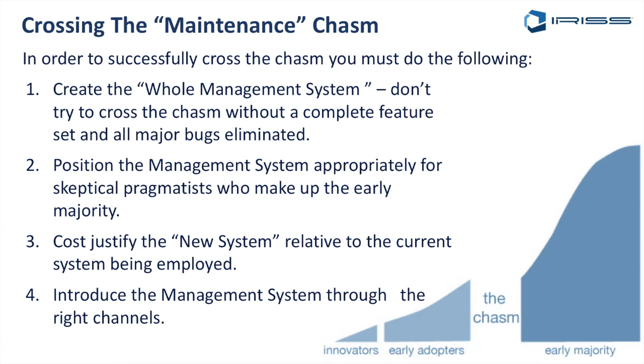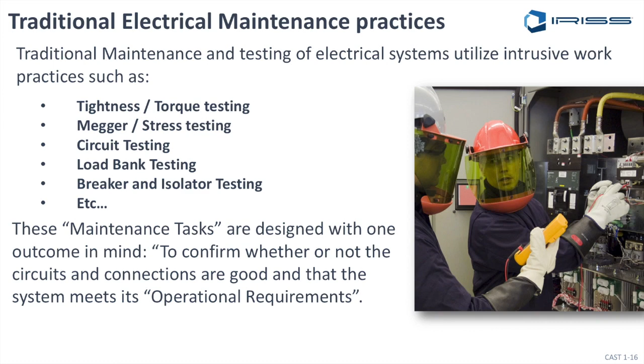When we look at traditional electrical maintenance practices, the traditional way of testing things, we do more hands-on. It's calendar-based: tightness and torque testing, Megger testing, stress testing, circuit testing, load bank testing, breaker and isolator testing, etc. These maintenance tasks are designed for one outcome: to confirm whether or not the circuits or connections are good. In maintenance, what we're trying to look at is the system, and if we can confirm it's meeting operation requirements and is safe, that's all we need to do.